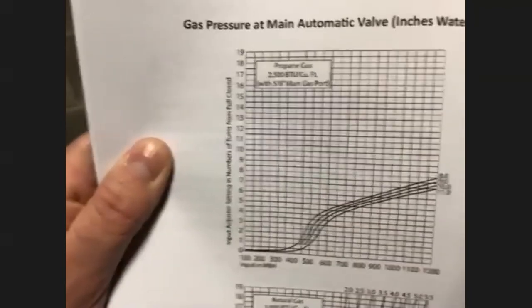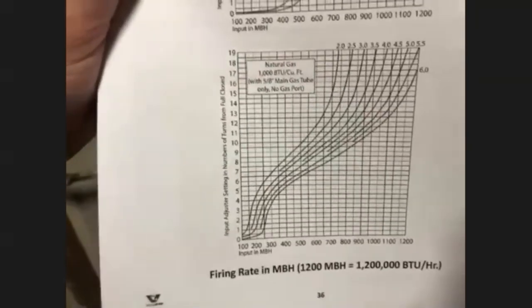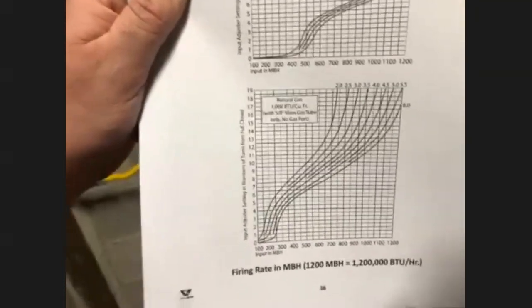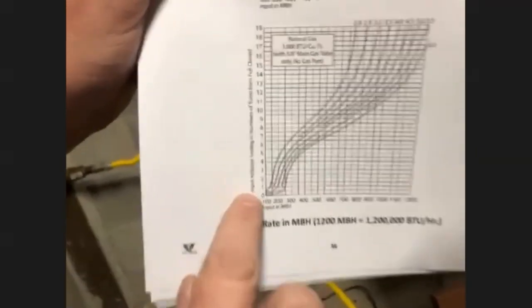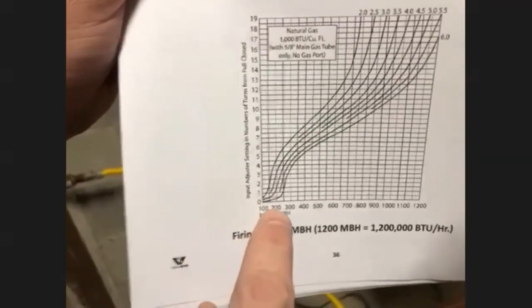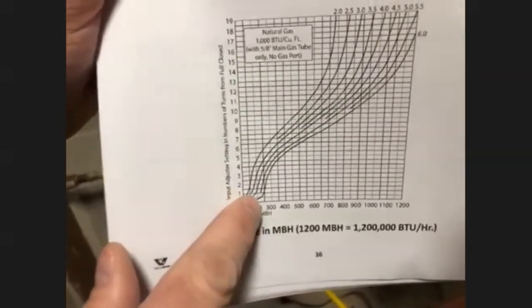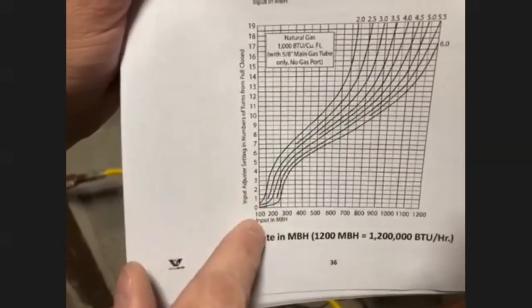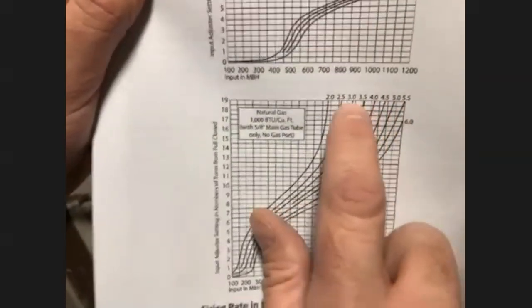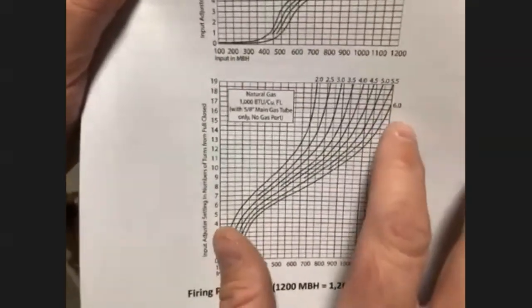In this manual, on the next page, we have a chart, a gas pressure. There's two different charts, one for natural gas and one for propane. And this tells you how many turns you need to do for that input adjuster. Right now we have a unit that's running off of natural gas. So we need 185,000 BTU. So we find that location, we come up, we determine how many turns we need to do based on input pressures.